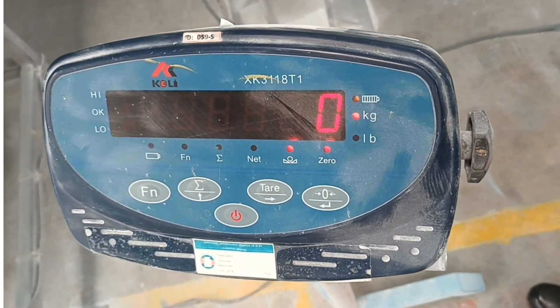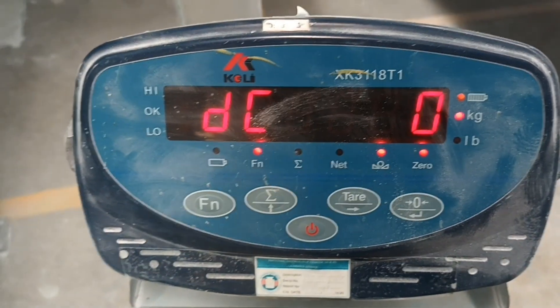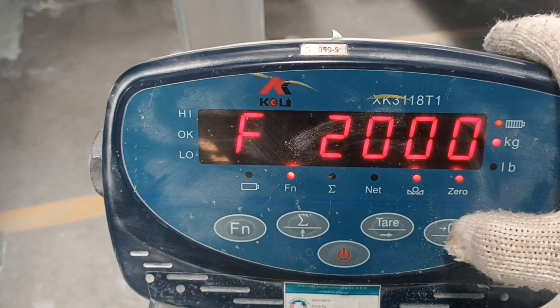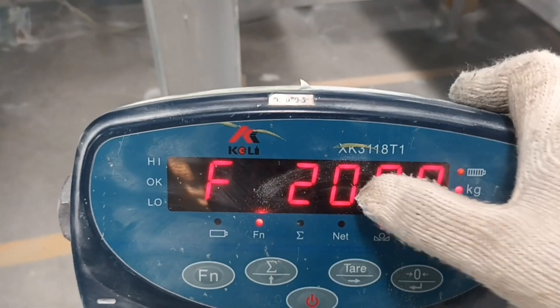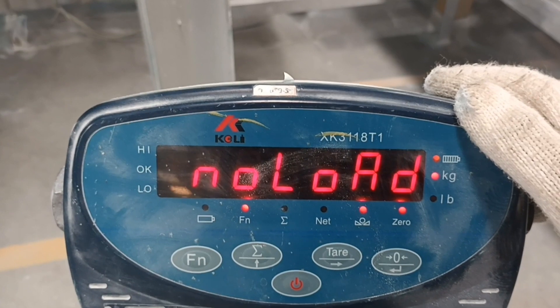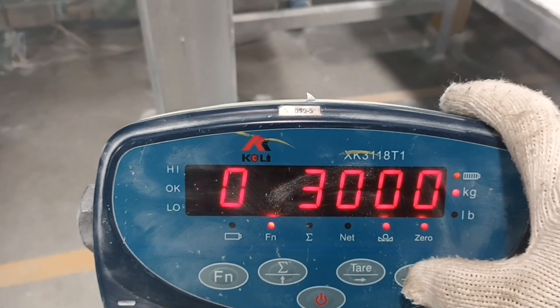Hello everybody. I will calibrate this platform scale. I will put the key card in. This shows CD zero and this shows the capacity. I put enter for no load — we have no standard on the pan. Wait a moment. I will put the key enter.